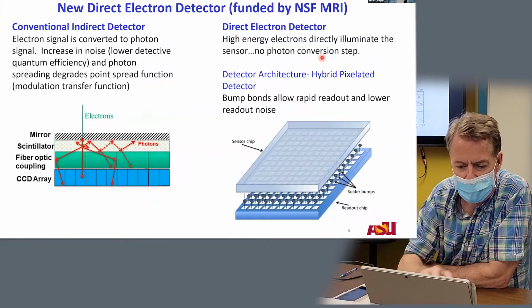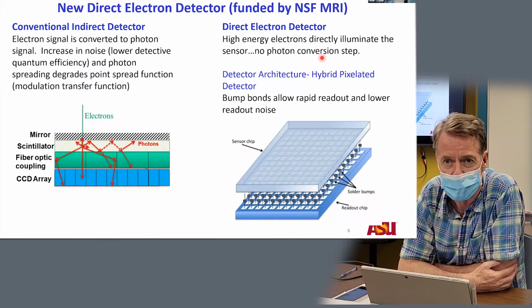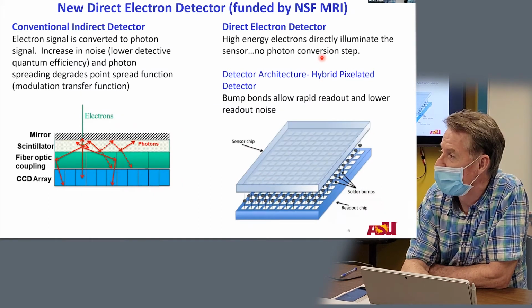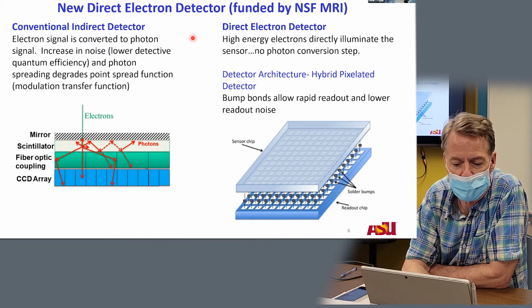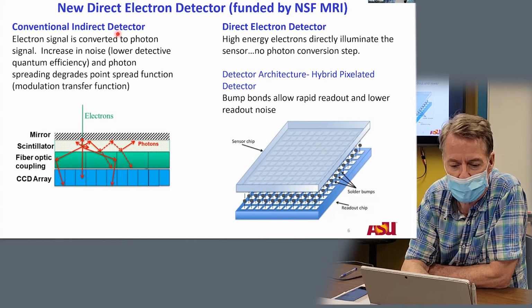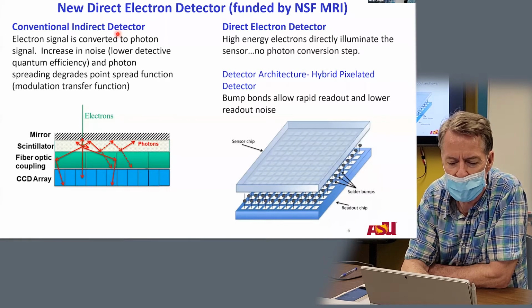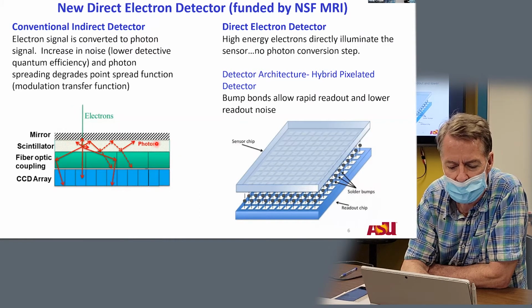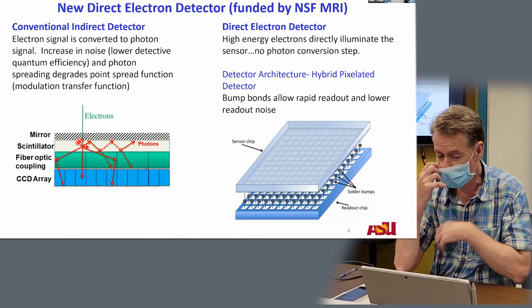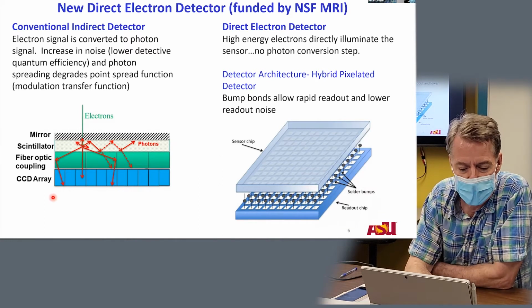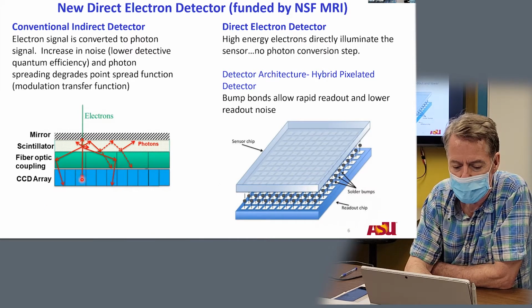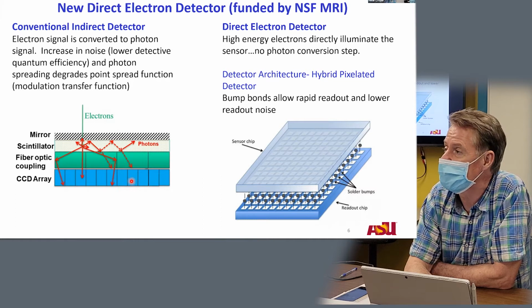This detector, funded by a National Science Foundation MRI, is what's called a direct electron detector. I put together a slide to illustrate what that is. Most of the detectors in electron microscopes today, the conventional detectors, are indirect detectors. That means the electrons first get converted to a photon signal. The electrons go into the scintillating material, and then those photons are transferred down to the camera element, the CCD array, similar to what you might have in your cell phone camera.